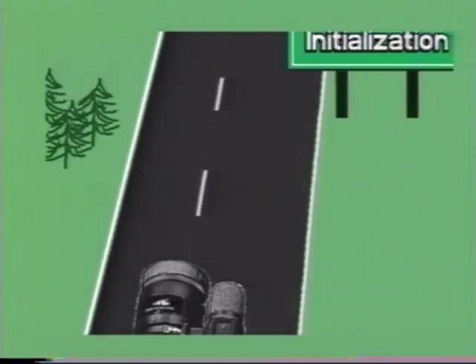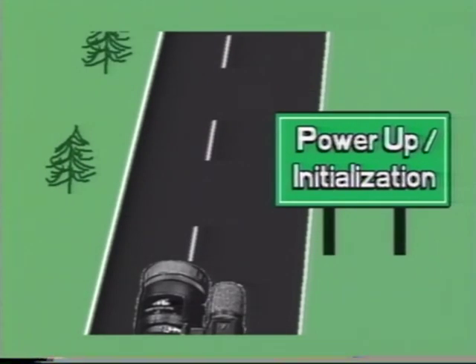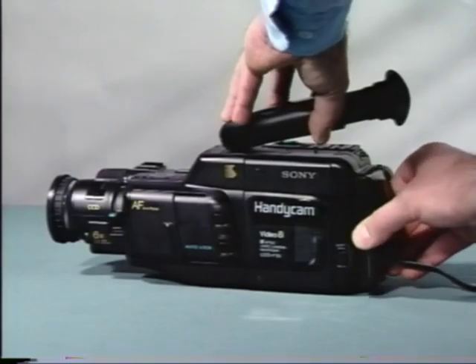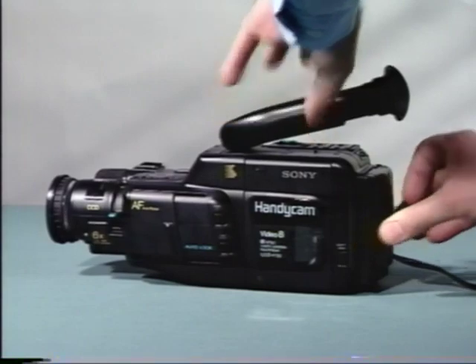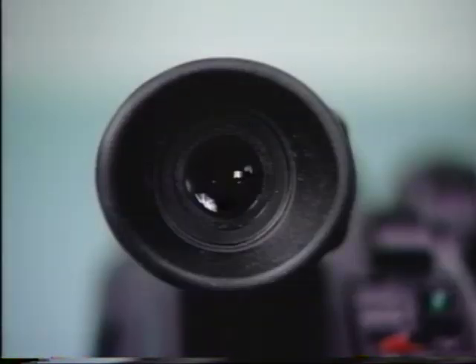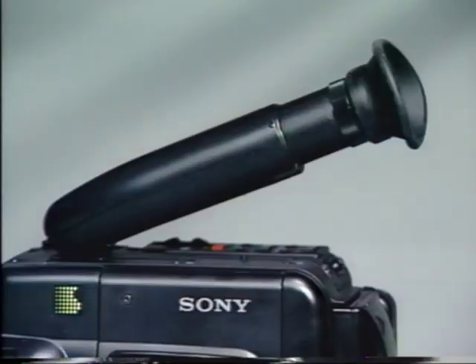To begin our troubleshooting journey, let's first go over the power-up sequence, which tells us a lot about the functioning parts of the VTR. With the power switch in the off position, apply power to the camcorder. The viewfinder should operate for about 1 second. This check is only valid if the viewfinder has not been damaged. Therefore, look for other power-up indications as well.